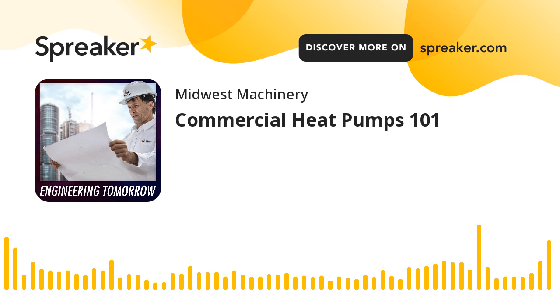All right, so we've got individual heat pumps per room, I guess you could say, right? Well, per room or per zone. If you think about it like a small apartment or a condominium, you're not going to have a heat pump in every room. You'll have one per apartment. So you might have it in a closet out in the corner of your living room, and then it's ducted up to serve the bedroom, the bathrooms, the kitchen, and the living room.